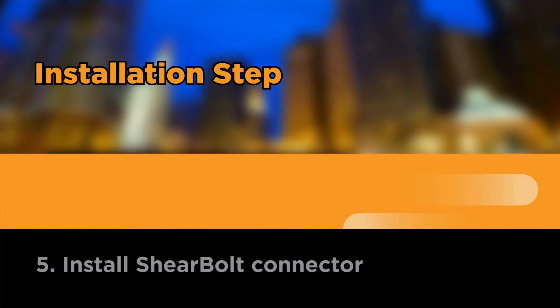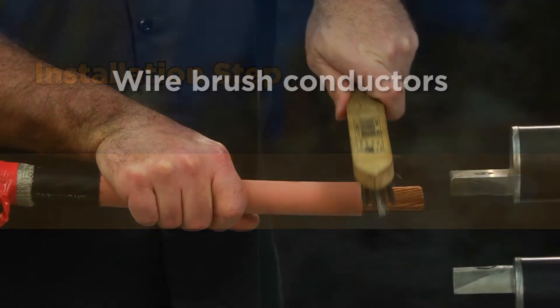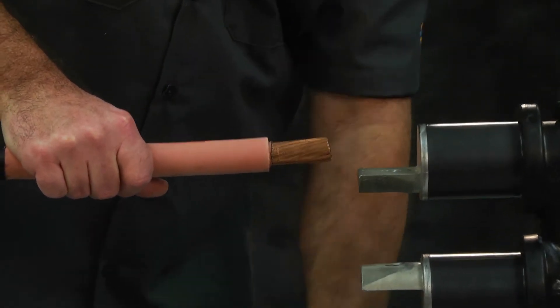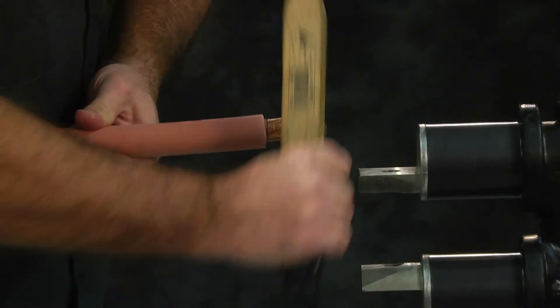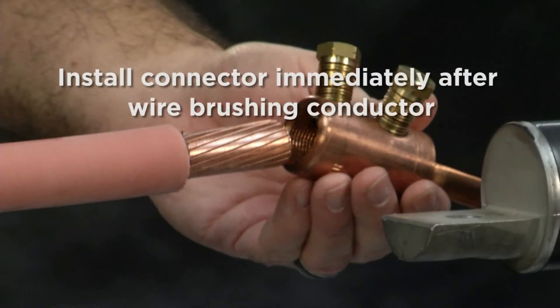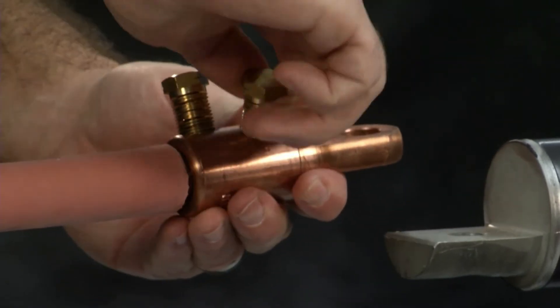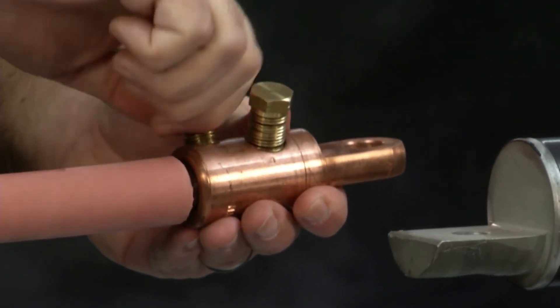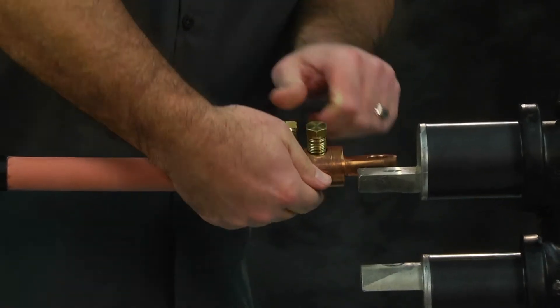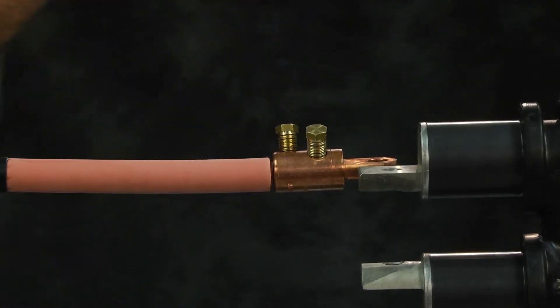Install shear bolt connector. Wire brush conductors. Using a wire brush dedicated for use on aluminum or copper conductors, thoroughly clean the bare surface strands of the conductor end. Cleaned conductor ends should be installed immediately after wire brushing to prevent reformation of oxides on all aluminum conductors. Insert conductors so that the insulation butts up with the end of the connector. Hand tighten the shear bolts so that the connector stays in place. Verify the dimensions between end of lug and semi-con cutbacks.